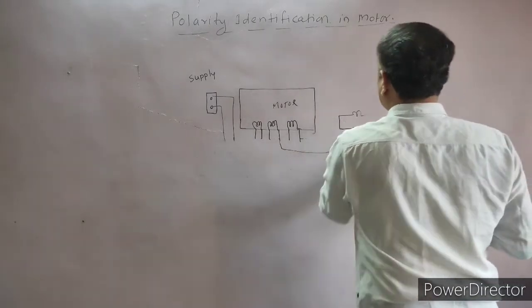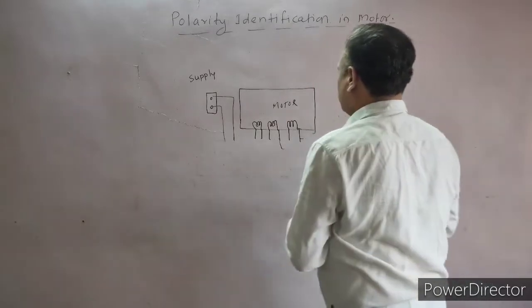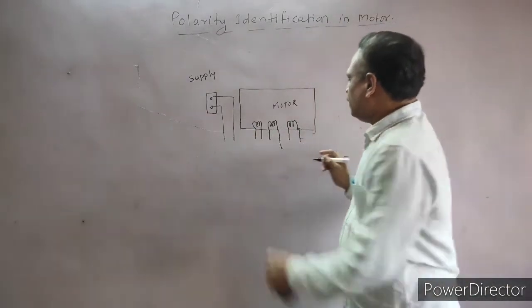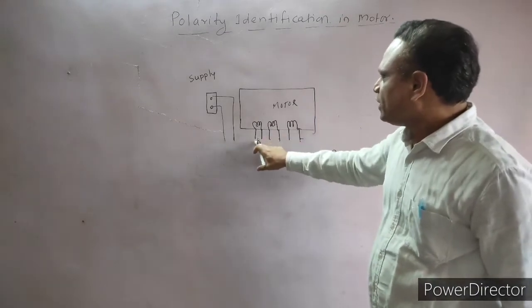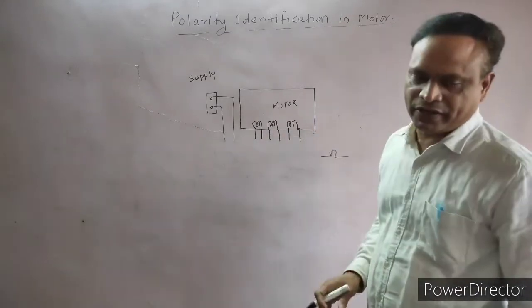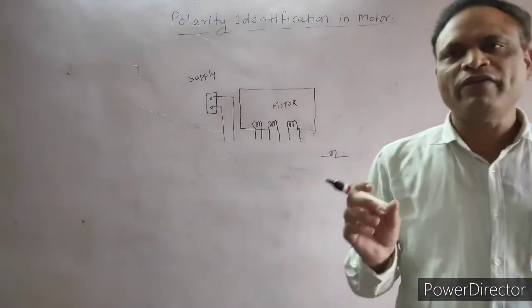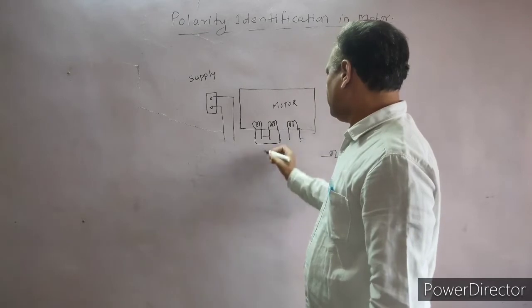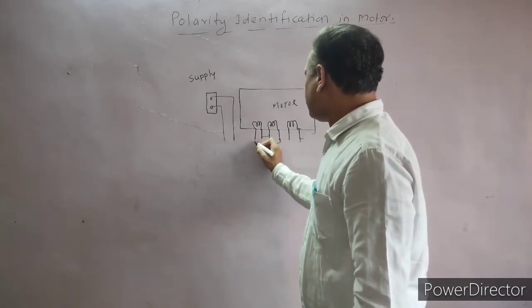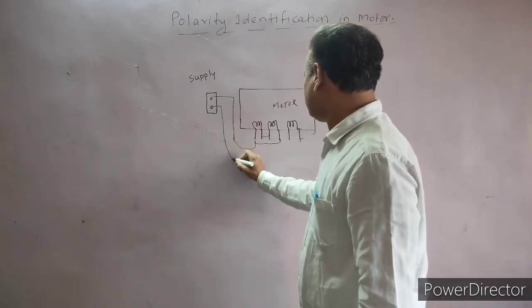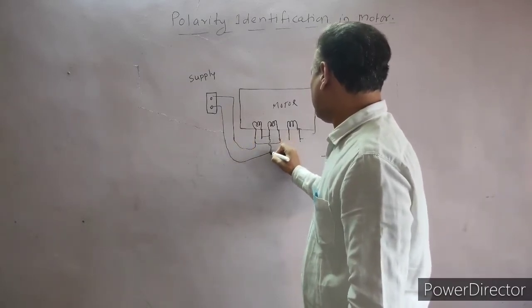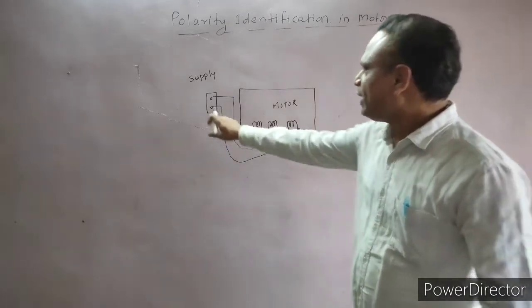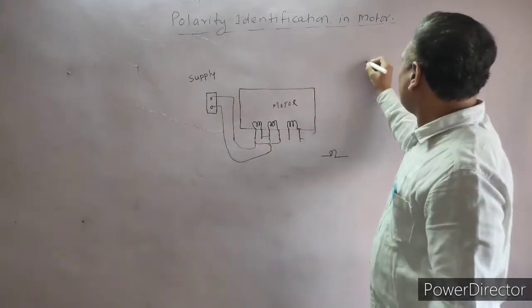This completes the work of the series lamp. Now we will use a simple lamp and a power supply for polarity testing. We have found the coil pairs, but we don't know which end is the starting end and which is the finishing end. To find this, we connect one terminal from the first coil to one terminal of the second coil, and then connect the power supply across the first coil.